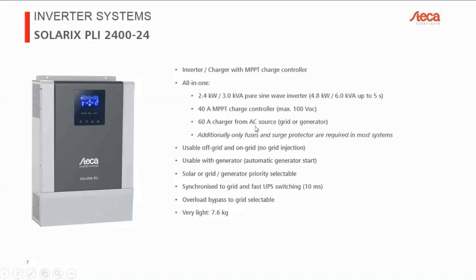Then we have a 60 amp charger from an AC source. So again, this could be either the grid or a generator, regardless. Of course, through programming of the unit, you can define priorities, such as when the grid should be used, when PV should be used, whether you want to prioritize one over the other, depending on your battery voltage, all those kinds of things. So all of this programming is done via the buttons directly in the menu of the device.